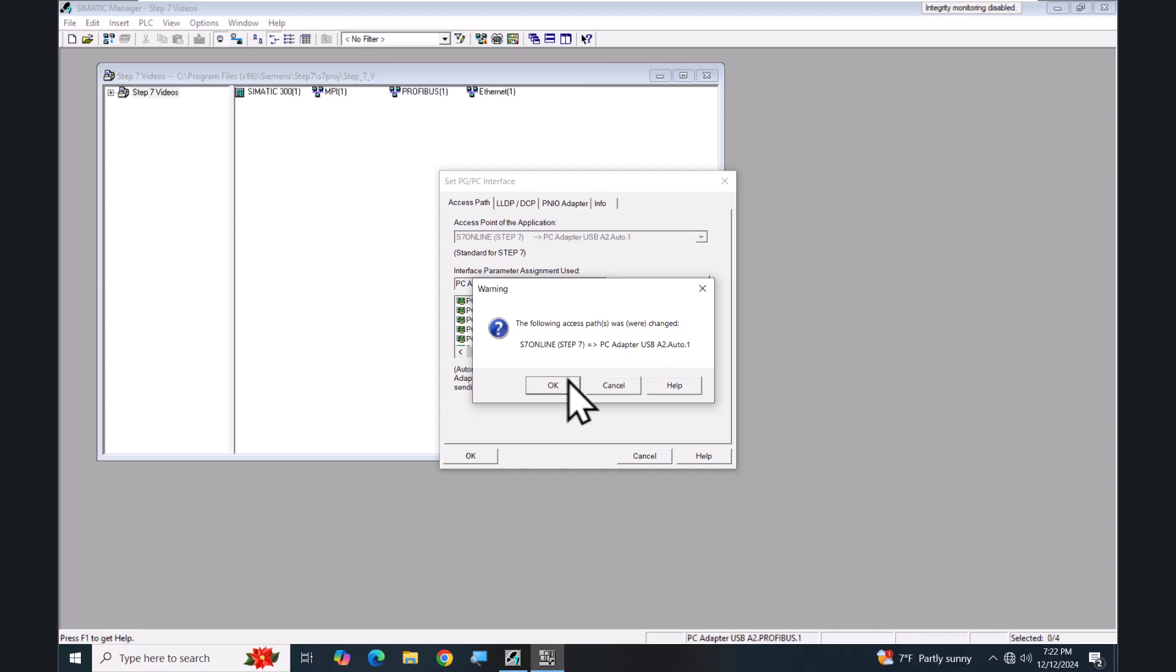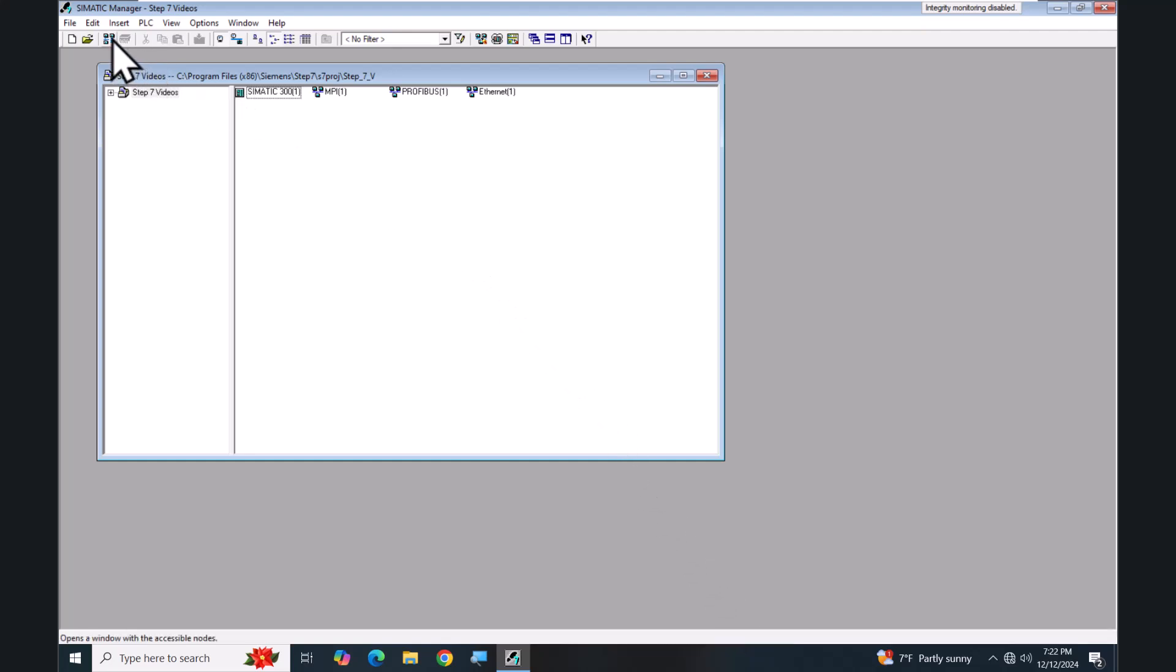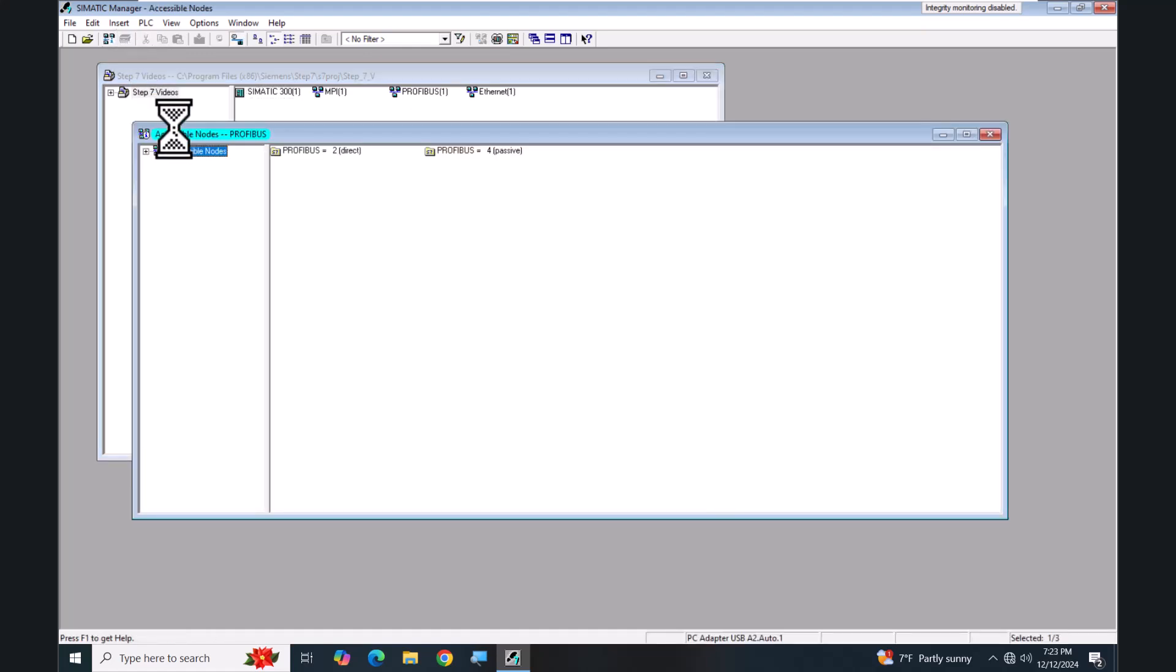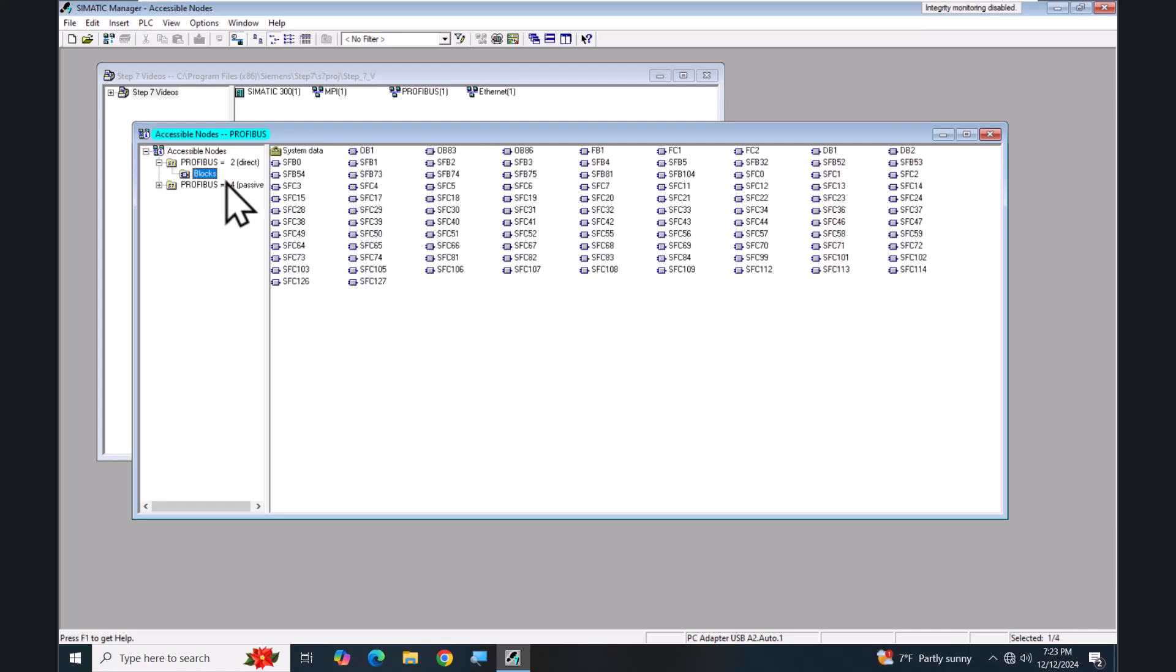I'll select Cancel and accept my parameter configuration. Now down in the status bar you can see I'm using the PC Adapter USB A2 in auto mode. I will select the icon to do Accessible Nodes. This will go out on the interface that I have assigned to my S7 Online logical connection and display all of the nodes that are available. I'll select the plus sign here and you can see I've got a PROFIBUS node at address 2. If I expand that out I can select the Blocks folder and then I can see the actual blocks in the PLC.